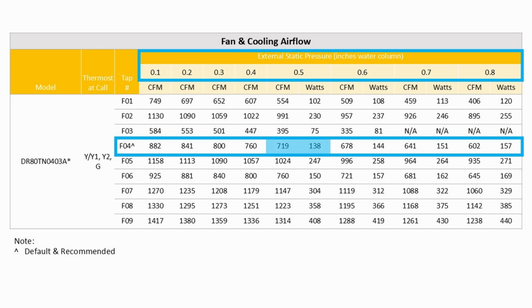This line shows that at 0.5 inches of static pressure, the CFM is 719 and the watts of power used are 138. At 0.7 inches of water column, the CFM is reduced to 641 and the watts of power used are increased to 151.